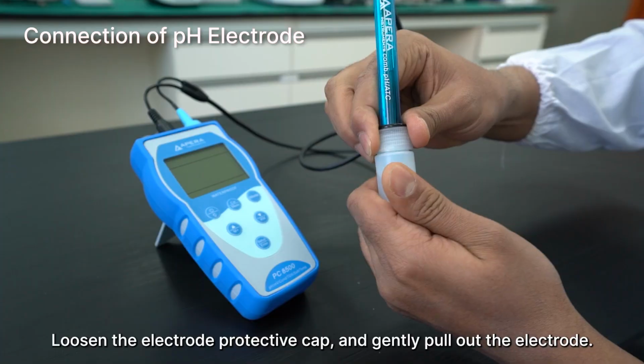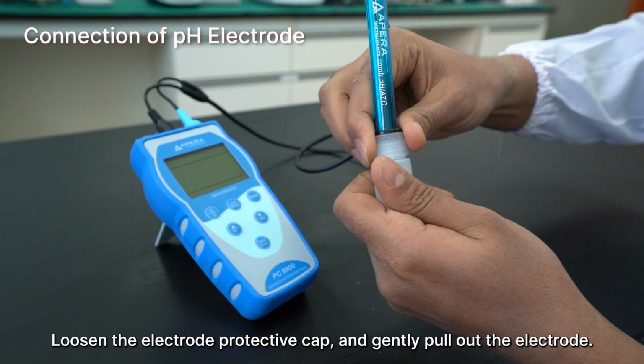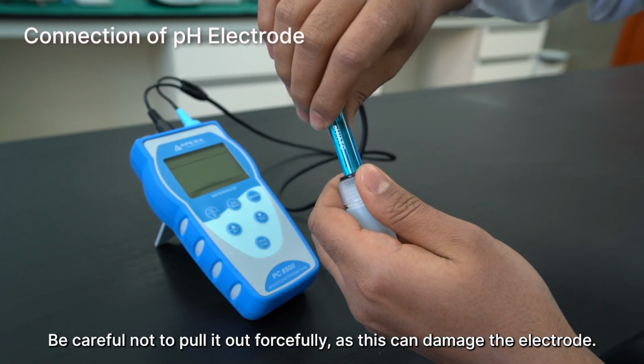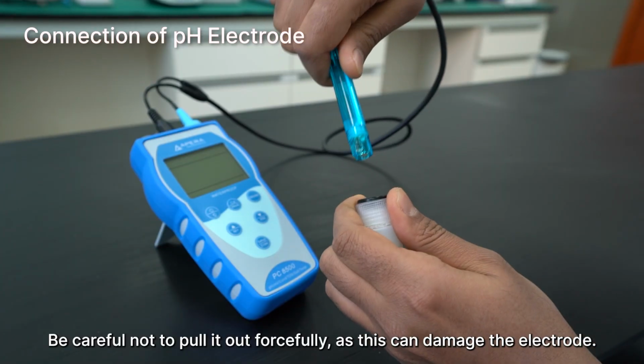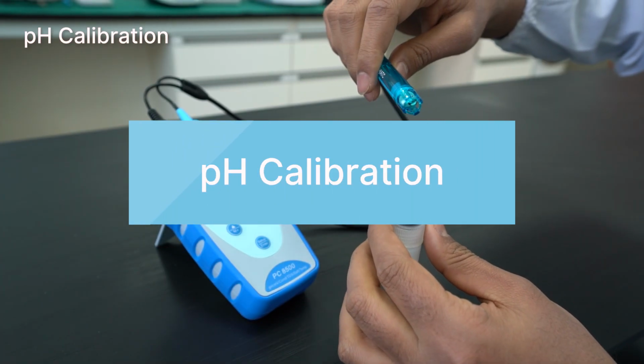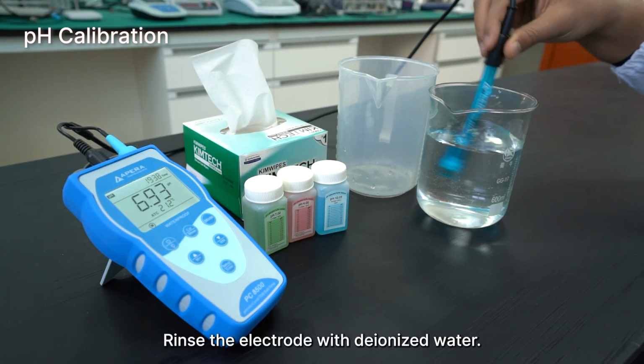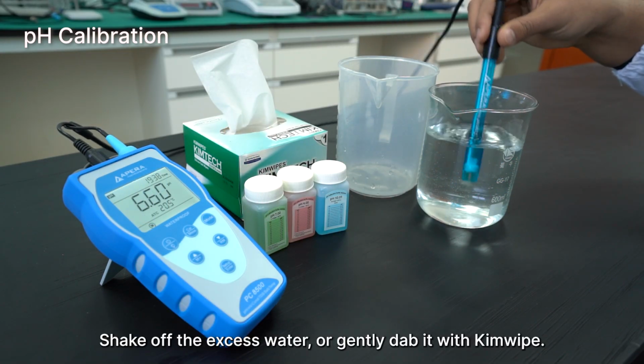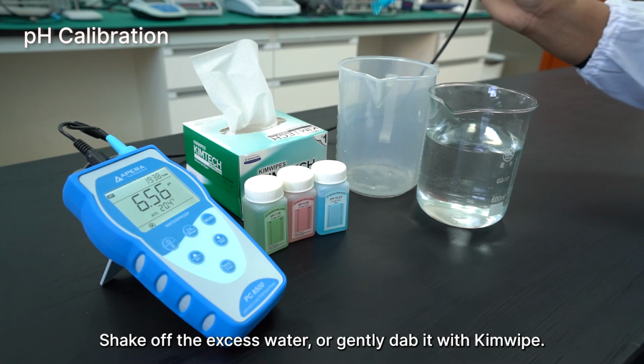Loosen the electrode protective cap and gently pull out the electrode. Be careful not to pull it out forcefully, as this can damage the electrode. pH calibration. Rinse the electrode with deionized water. Shake off the excess water or gently dab it with Kimwipe.